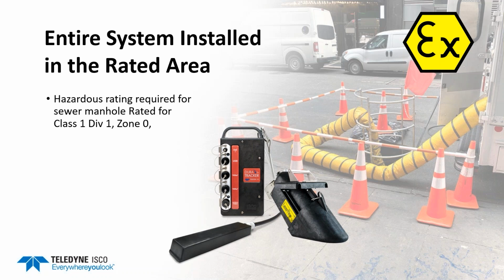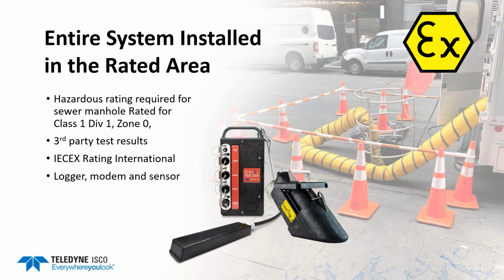So first, let's cover when the entire system is installed in the rated area. The equipment should be rated for Class 1, Div 1, Zone 0, ATEX rated. And as we're shown here, the logger is IS rated, as well as the different sensors that you would mount into the collection system. All of our equipment has been third-party tested to make sure that it meets that qualification. It meets the IECEx international rating. And what we're looking at here would be the logger, a built-in modem, and the different types of sensors that can be used in the sewer system.